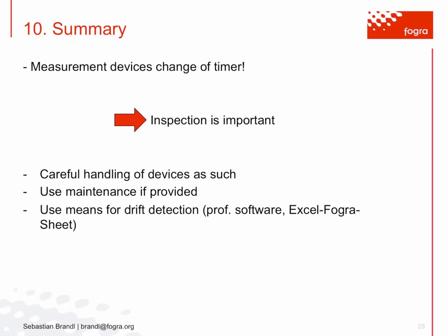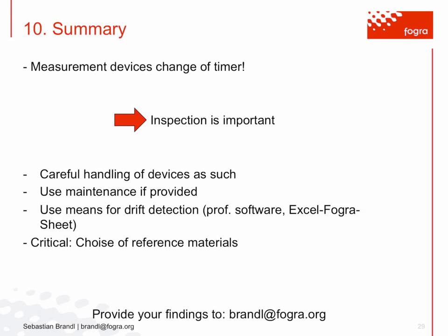What we sometimes find is that a device falls down and nobody reports it, then later you use that measurement device and it provides some readings, but no one really had the courage to say, "Oh, I had a problem with it. It fell down, and it might provide wrong readings." Now you don't find it, or you find it when it's too late. And we would like to avoid this.